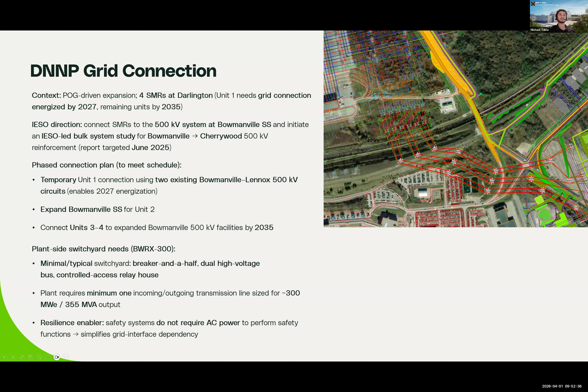From the BWX perspective, the switchyard requirements are intentionally minimal and conventional, relying on a breaker-and-a-half dual bus arrangement with controlled access to protection and controls relay houses. Currently, BWX is connecting to the 500 kV system at an expanded Bowmanville switching station, which also introduces additional circuits going to other parts of the system closer to the Greater Toronto Area. We're working to develop the transmission line routing and path. We're next to the Darlington nuclear generating station, which also connects to Bowmanville, so they're expanding Bowmanville to connect the SMR as well as other lines in Ontario.